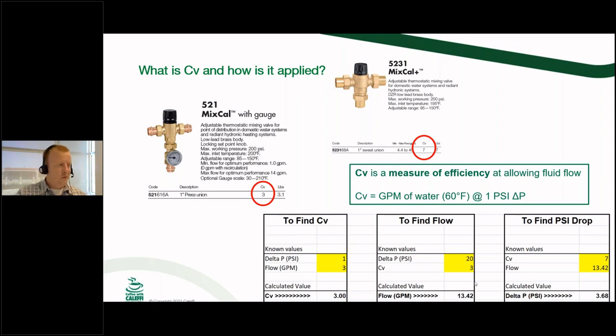It's not common to have a 1-inch domestic hot water system and then have a 20 PSI differential across your valve. In many scenarios, engineers will really shake their head at that. They're usually looking for a 5 to 10 PSI pressure drop across that valve, and usually no more. So if you have 45 PSI coming into this mixing valve, you're going to have 25 PSI coming out. And obviously that's a problem.